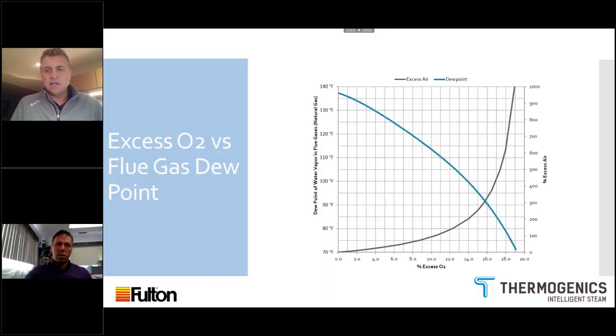If I can just make one note about one of the most common issues I see in condensing hot water retrofit in the current landscape, it's this slide right here. Can everybody see that okay? Yes, it's good. So today we do everything we can to load match. BTUs out, we're going to try and put them in the exact same manner. That translates over to turn down, as you noted so well in the presentation, how critical turn down in a boiler plant is to match that load usage, especially as we transition between seasons.